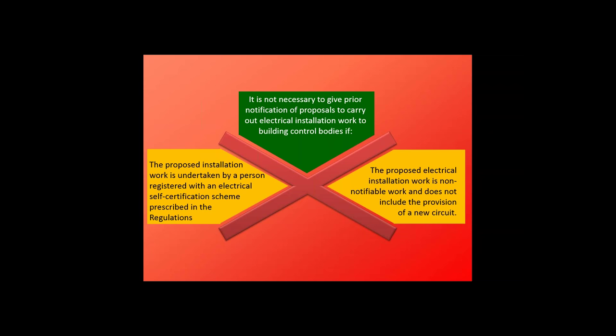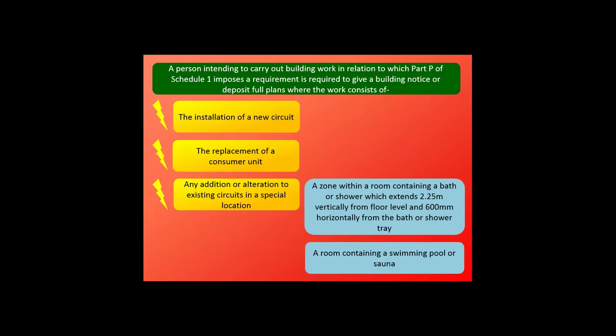However, some work does need notification. That work is basically wherever we're installing a brand new circuit, or if we're replacing a consumer unit — those are obviously key risk areas and fairly major works. Also, any work that involves alteration to a circuit in a special location needs notification. Special locations are defined in the approved documents as generally those where there is a higher level of risk, such as rooms with a bath or shower, where we create a zone 2.25 meters high and 600mm wide from the water source. Similar provisions apply to swimming pools, saunas, and the like.